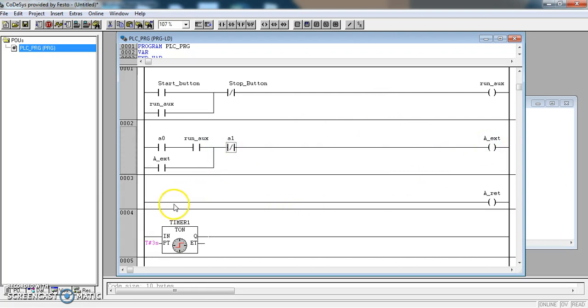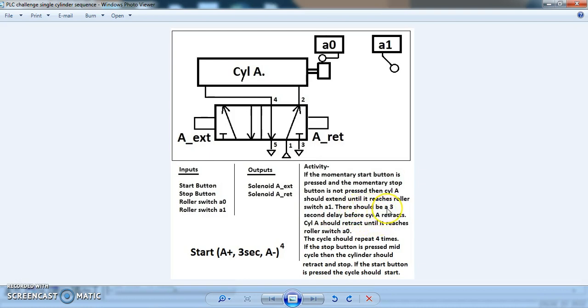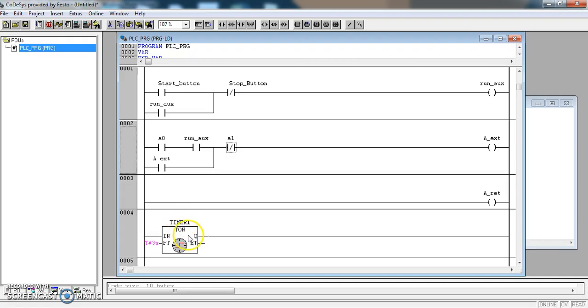The A retract solenoid needs a signal — A retract needs to come on once our timer has elapsed. It says there should be a 3-second delay before cylinder A retracts. So the 3-second delay is controlled by the timer. The timer will give a signal out on this Q value, and that signal will be the trigger to get A to retract.